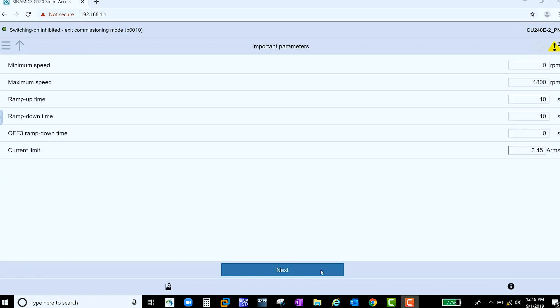The next page requests your important parameters. What is your motor's minimum and maximum speeds? What are the ramp-up and ramp-down times? And what is the max current that your motor should see?